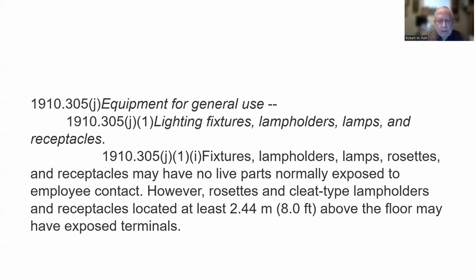Equipment for general use: lighting fixtures, lamp holders, lamps, and receptacles. Fixtures, lamp holders, lamps, rosettes, and receptacles may have no live parts normally exposed to employee contact. I like that: no live parts. However, rosettes and cleat type lamp holders and receptacles located at least 8 feet above the floor may have exposed terminals. My rule on that one: if it's within 7 feet of the floor work surface, you can touch it and it can hurt you, it must be guarded. That's whatever, electrical, mechanical, anything. That's a good rule to follow.